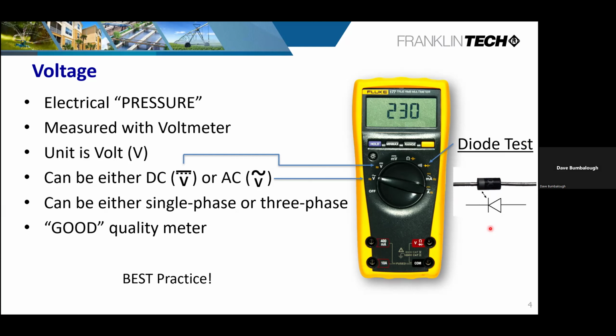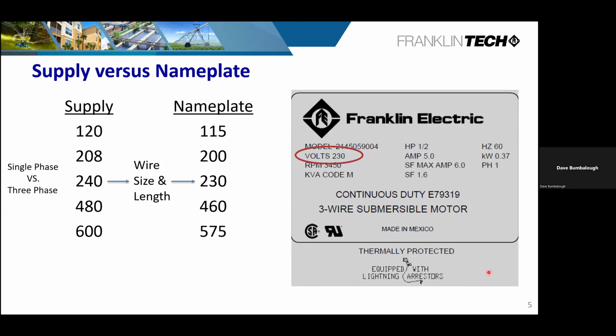In our testing, especially when it gets to some of the advanced controls like drives and VFDs, we can check the components inside to see if there is an issue on the incoming side, the outgoing side, or both. That will help us determine what to identify and what our next procedure is going forward. On top of looking at DC voltage and AC voltage, we're now going to do a diode test and determine what's going on in that system.